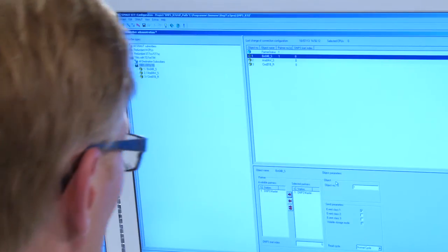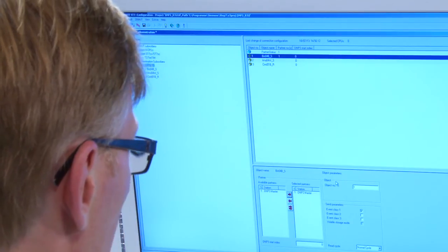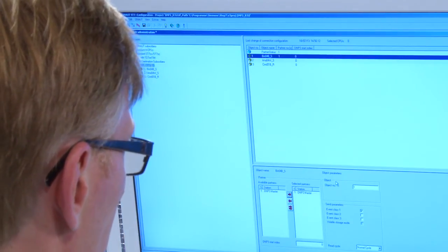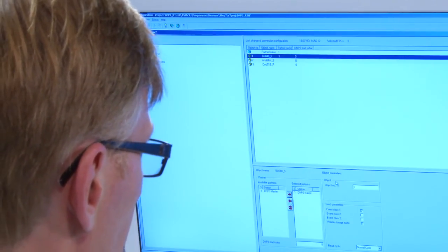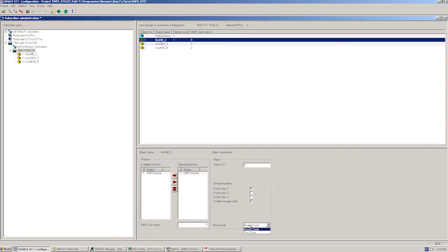As a result, such values will not be lost in the case of a communications failure. Since we have parameterized the first DNP3 object of the binary input type, we can keep the index addresses with the default value 0. Selecting a fast read cycle ensures that the values from the CPU will be applied immediately.